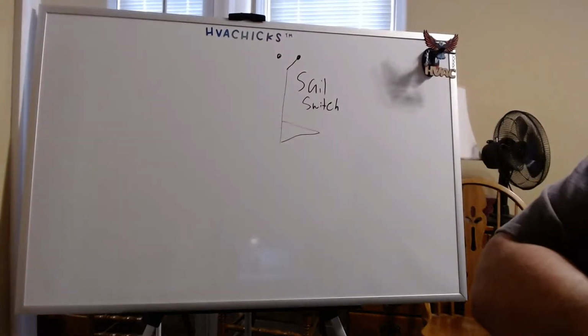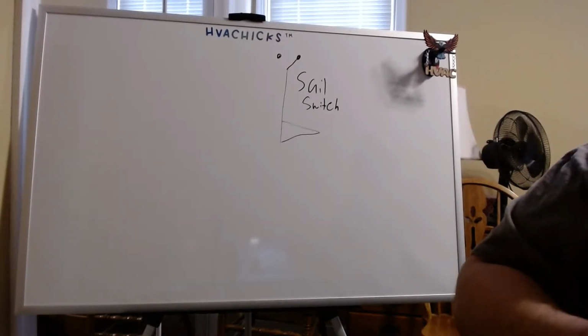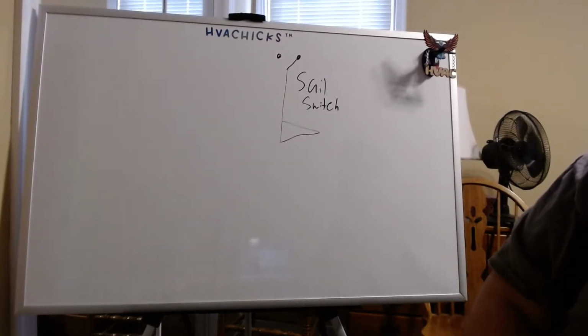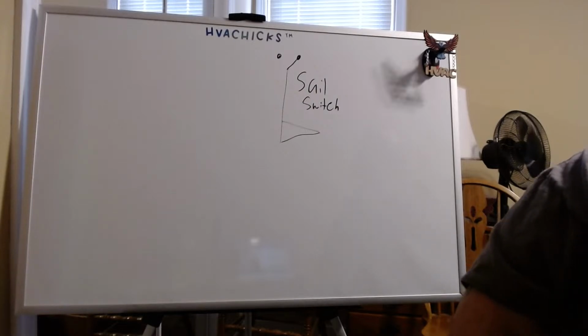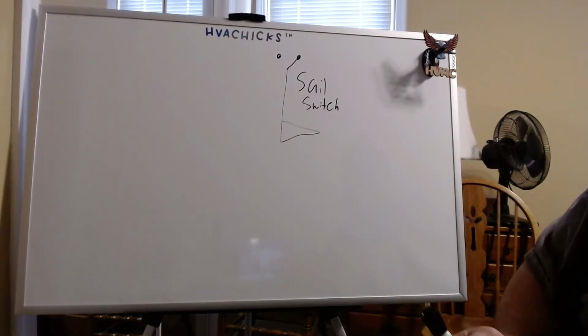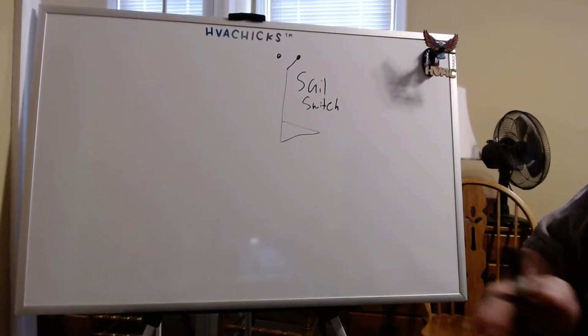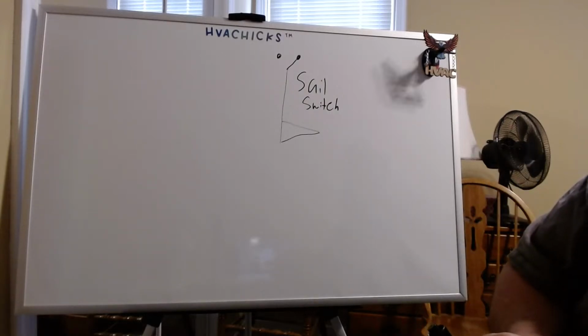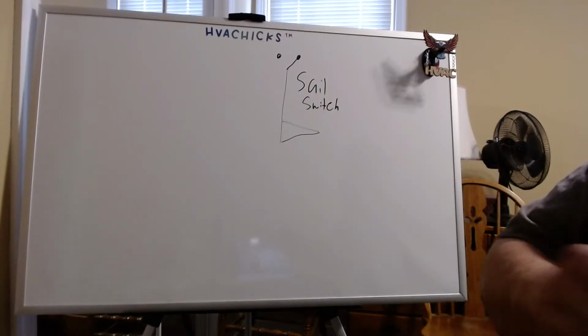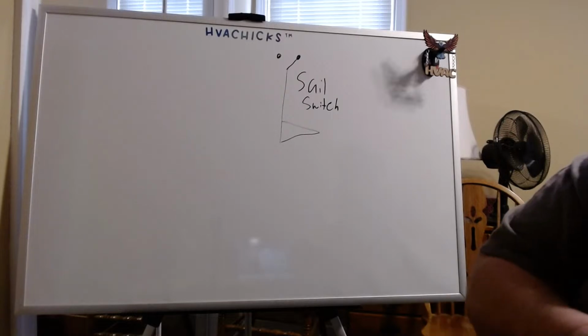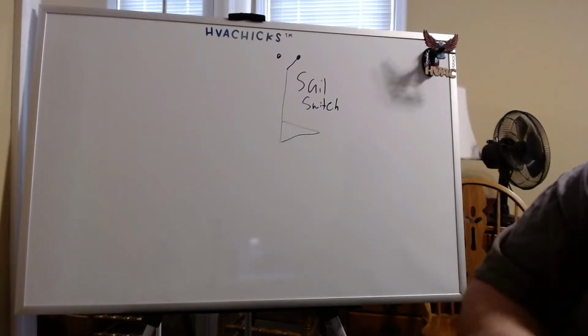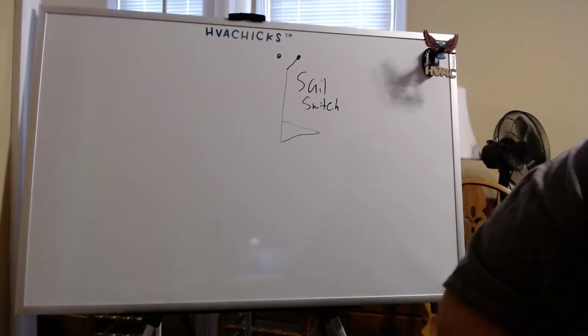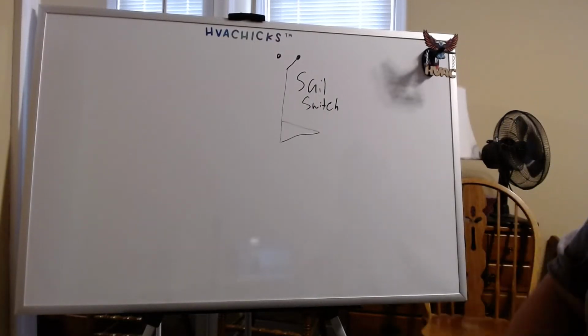Basically, what a sail switch does is it checks for movement of air. Back in the day, we used to have electronic air cleaners that had to have a sail switch on there in order to show 'hey, I'm moving air, let's bring on the electronic air cleaner.' Or you'd have sail switches for certain things, like to prove air is moving before the heat strips would come on in big commercial units. Yes Mac, that's actually the book I taught out of at school.